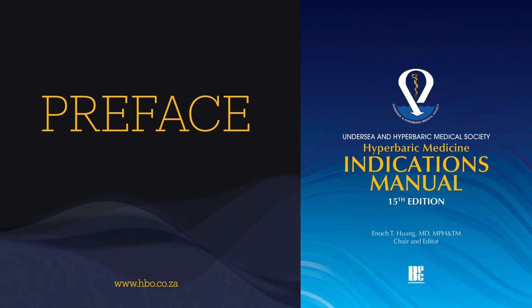And here's where the manual introduces that slight refinement on the pressure threshold we discussed earlier. Right. It states that current information indicates that pressurization should be to 1.4 atmospheres absolute or higher for a treatment to even be considered hyperbaric oxygen therapy at all. Okay, 1.4 ATA is the minimum floor to even use the term hyperbaric oxygen therapy. Exactly. It provides that minimum barometric pressure, distinguishing any form of hyperbaric exposure from just normobaric therapy. But it's crucial to remember the nuance here. While 1.4 ATA is presented as the minimum threshold to technically fall under the umbrella term hyperbaric oxygen therapy based on current info, the manual's earlier definition for safe delivery and proven clinical application for the accepted indications specifically requires not less than 2.0 ATA. Precisely.